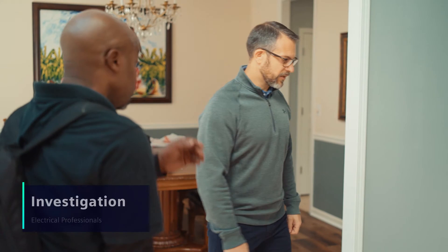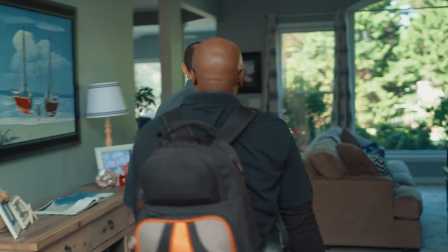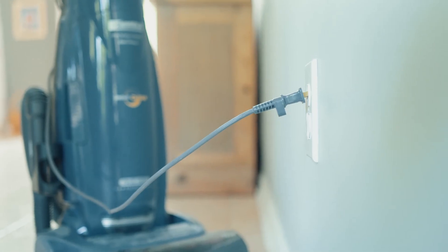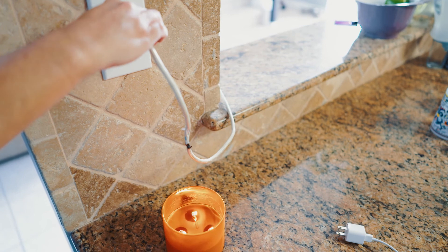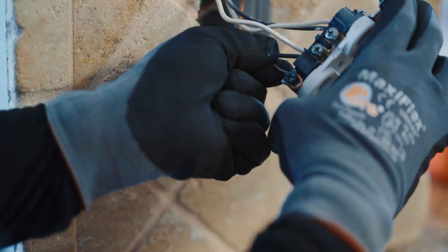Be sure to give them the answers to the general diagnostic questions. Diagnostics of electrical circuits should only be done by a qualified electrical contractor. The first step in finding the root cause of a circuit breaker trip is to eliminate the most common and routine causes — things like loose connections, misapplied or damaged appliances, and incorrectly wired outlets and circuit breakers.